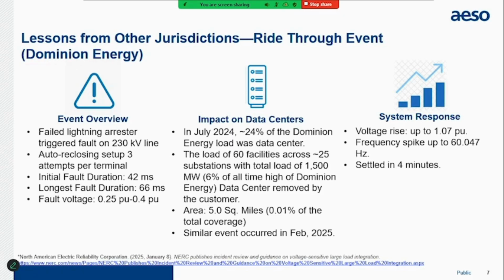What happened was there was a permanent fault on one of the 230 kV lines, and after three attempts of auto-reclosing, the fault was cleared. But during the disturbance, about 1.5 gigawatts of data center load disappeared from the grid, and Dominion Energy saw a sudden loss of load.